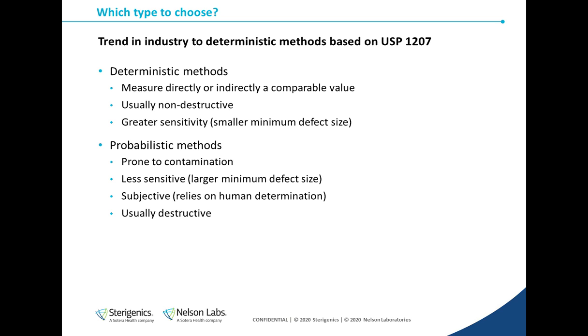The latest version of USP 1207 recommends deterministic methods for CCI testing, and this is really driving a shift in the industry towards deterministic methods. You can see why deterministic methods are preferred. They're giving a measurement, which not only tells you if you passed or failed the test, but how close or maybe how far you are from that magic pass-fail threshold value.